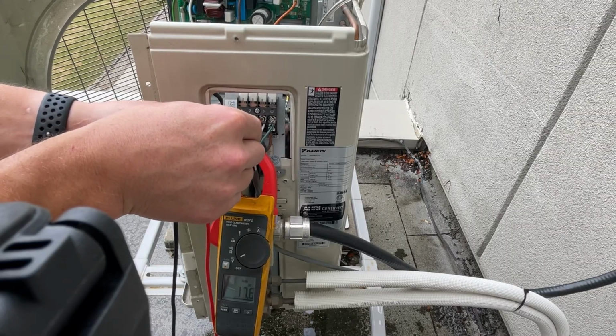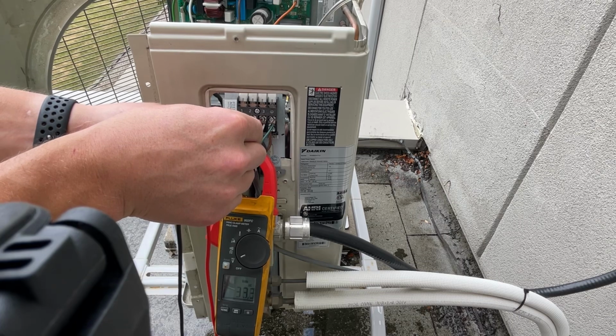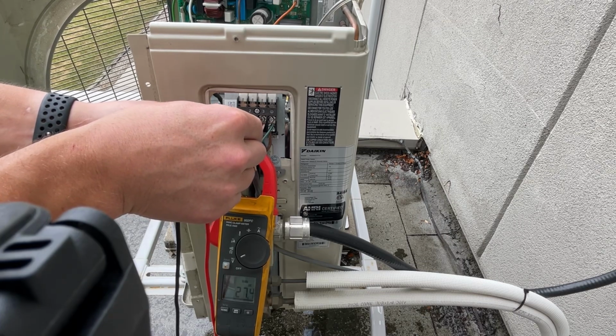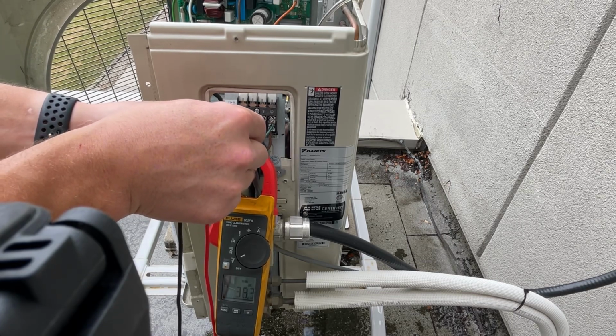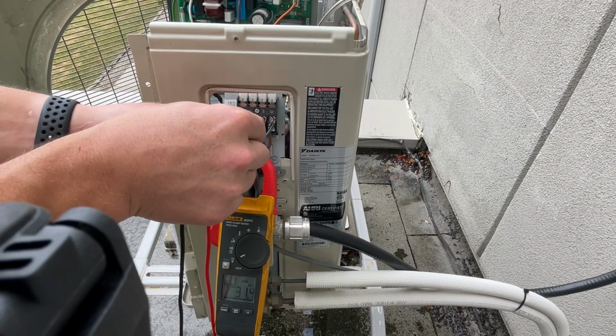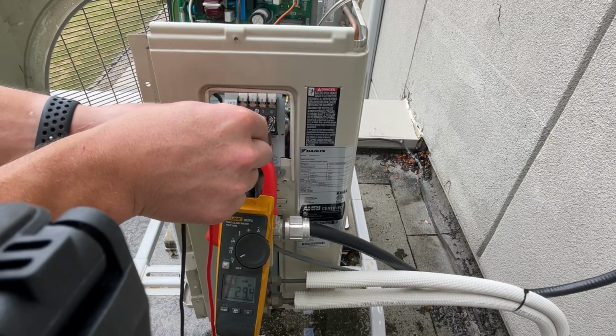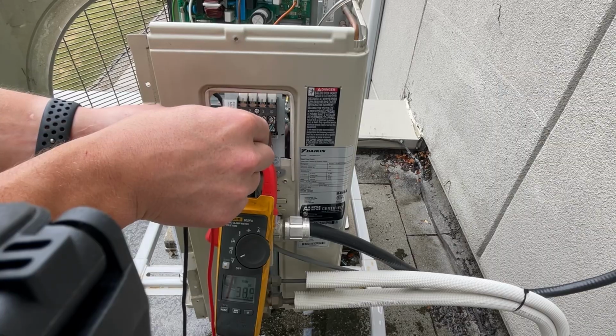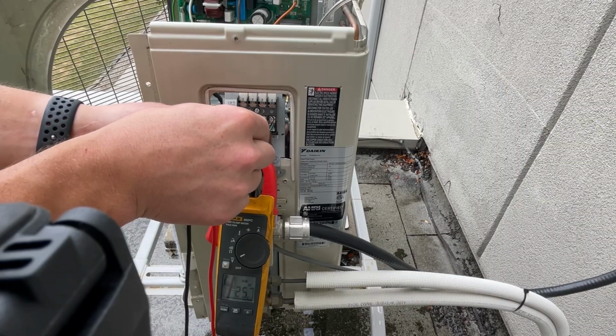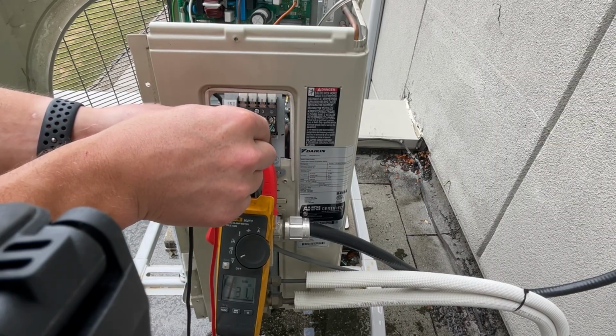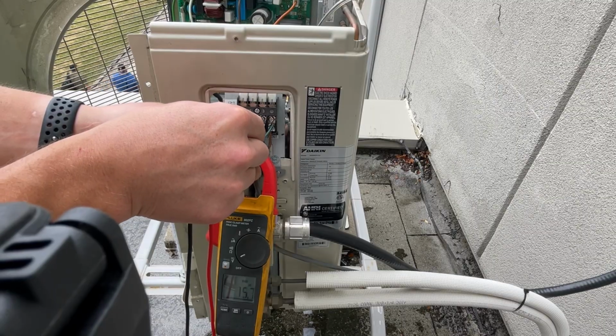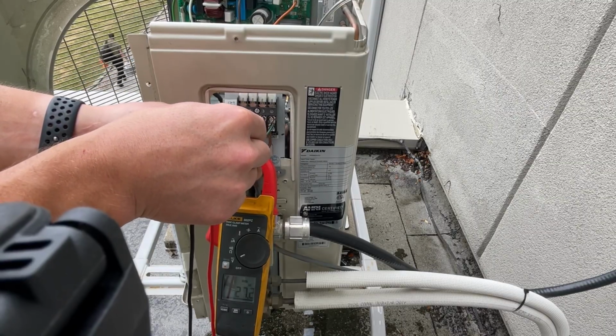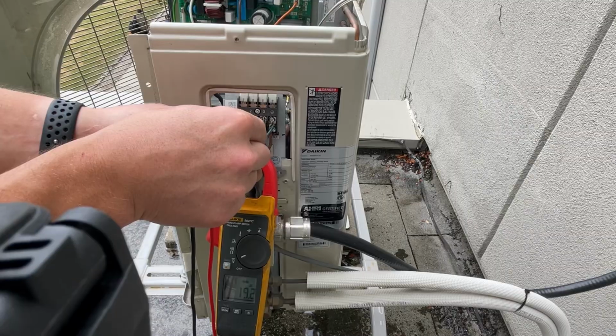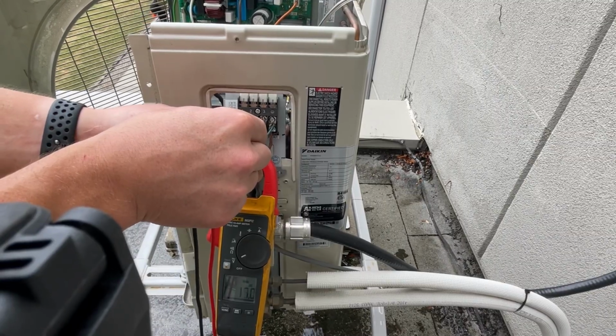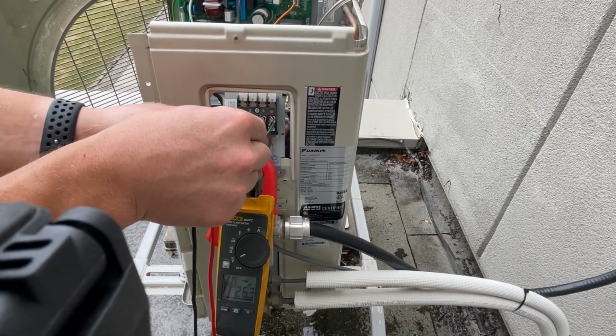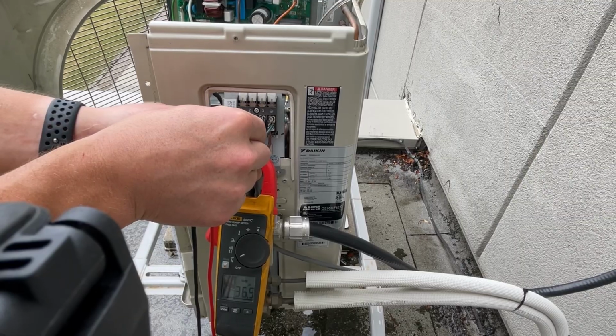You see that? 26, 29, 30, 17, 39, 23. You see how it's all over the place? We're going to be looking for a pulsing voltage starting at 0 to 9, then from 10 to 19, then from 20 to 29, 30 to 40, so forth and so on. But remember, never above 45 volts. And we're nowhere consistent here. We are all over the place. 39, 26, 23, 32, 17.